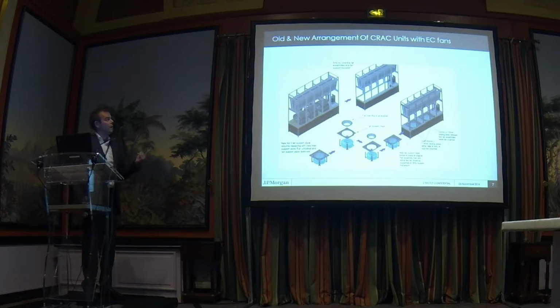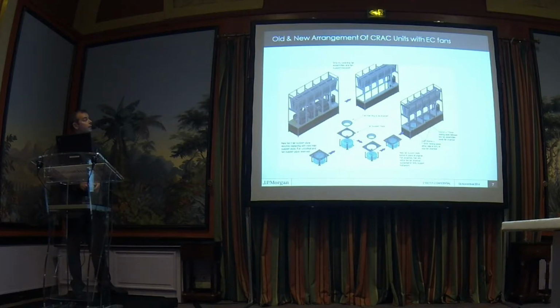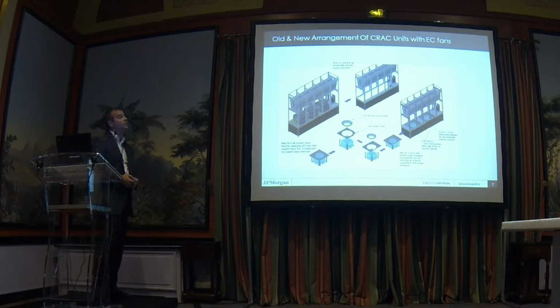Had twin V-belt drives on each one, so I had 6 drives, 6 V-belts running. You stand there with a thermal camera and I could see these V-belts just glowing, just losing heat, losing energy, just from friction. So we come up with a solution, put in EC fans, and the secret to this is the bigger the better. The bigger the fan, the better efficiency you get out, and the lower the output you got right out to do it.